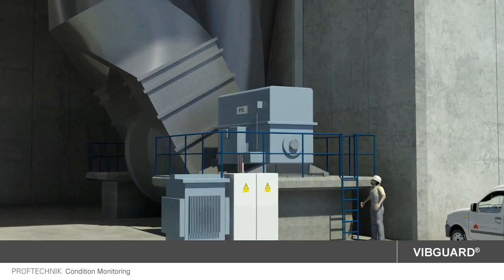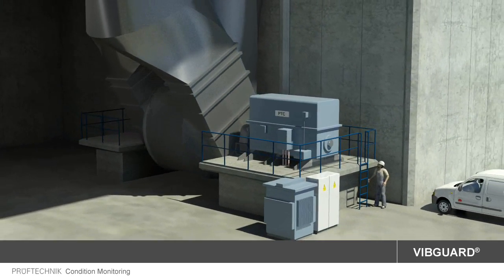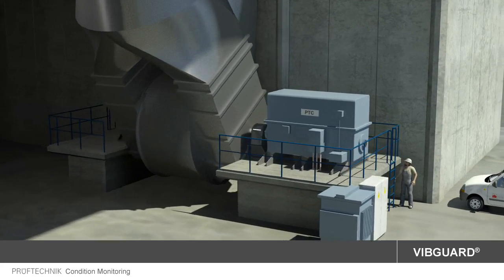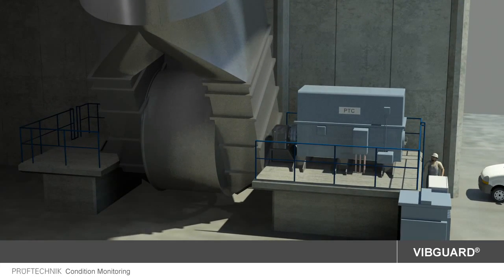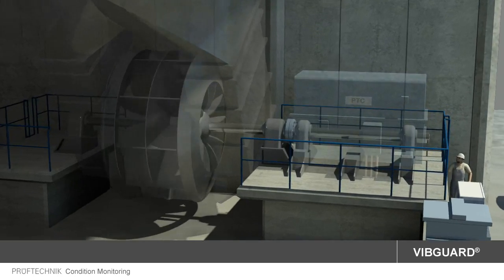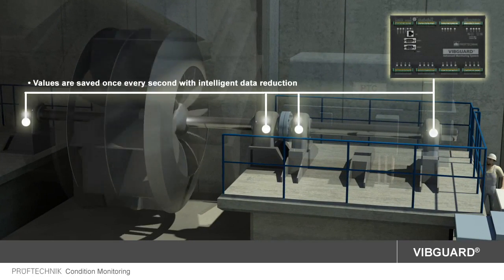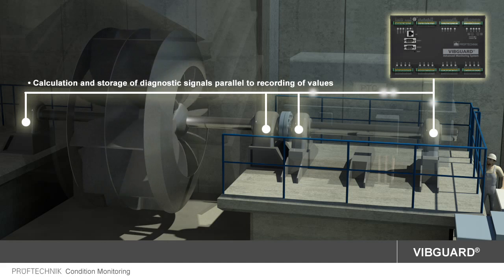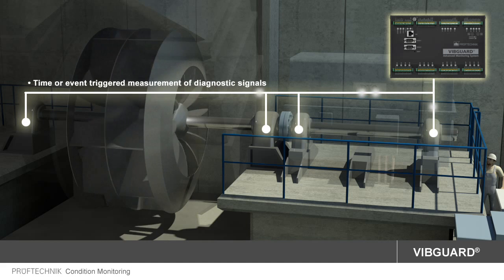Based on the example of a large process fan, we would like to demonstrate the diverse functions of VIBGUARD. The motor and fan shaft are monitored at four measurement locations. Overall values are recorded seamlessly and synchronously and are stored every second. Due to intelligent data reduction, only significant changes are saved in order to keep the data volume within a manageable level. At the same time, frequency-selective information from all channels, such as the FFT spectrum or the envelope spectrum, are calculated and saved.